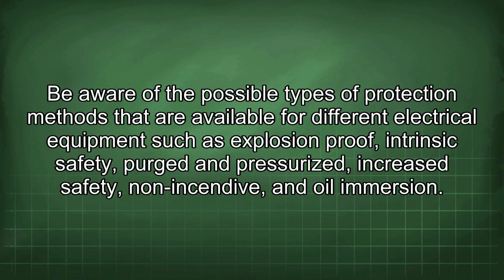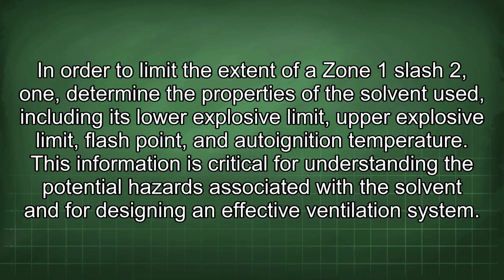Be aware of the possible types of protection methods that are available for different electrical equipment, such as explosion-proof, intrinsic safety, purged and pressurized, increased safety, non-incendive, and oil immersion. In order to limit the extent of Zone 1/2: 1. Determine the properties of the solvent used, including its lower explosive limit, upper explosive limit, flash point, and auto-ignition temperature. This information is critical for understanding the potential hazards associated with the solvent and for designing an effective ventilation system.